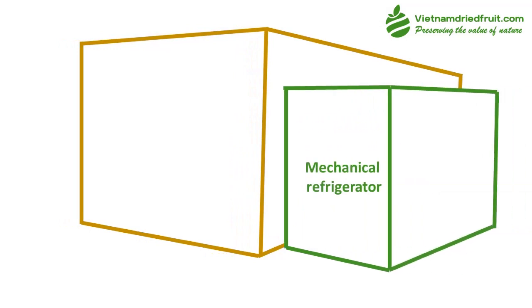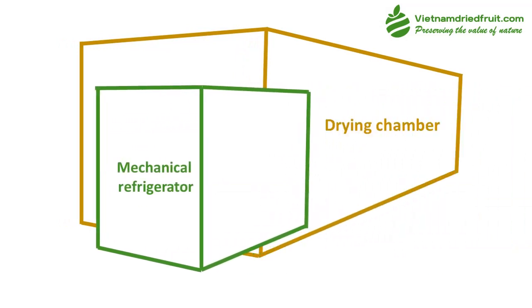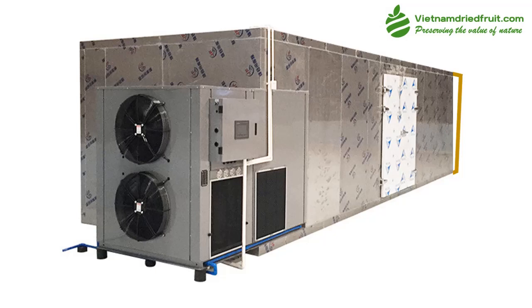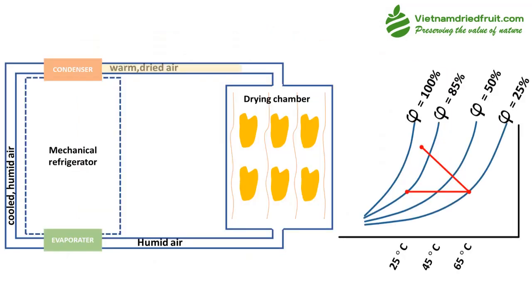In a heat pump drying system, aside from the drying chamber, the system is equipped with one or two mechanical refrigerators depending on the capacity. The refrigerators serve to reduce the temperature of the air coming out of the drying chamber, and the water vapor is condensed into liquid water, which is then removed.